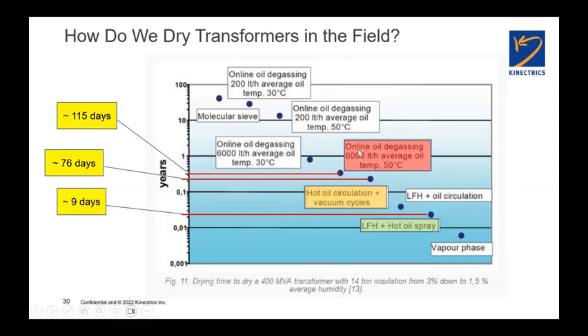So I'm only taking half the water out in this scenario. If I use an oil processor only, 6,000 liters per hour, that's a pretty big oil processor, putting oil out at 50 degrees C, you can see here that the time to achieve that moisture reduction is, this is in years, logarithmic on the vertical axis, 0.1, 0.2, 0.3, it's 115 days roughly. If I do the rip and dump, which is the modification, it's significantly better, but still 0.1, 0.2, and change, 0.23, 76 days. If I do low frequency heating coupled with the hot oil spray, 0.02 years, 9 days. Order of magnitude difference in effect.